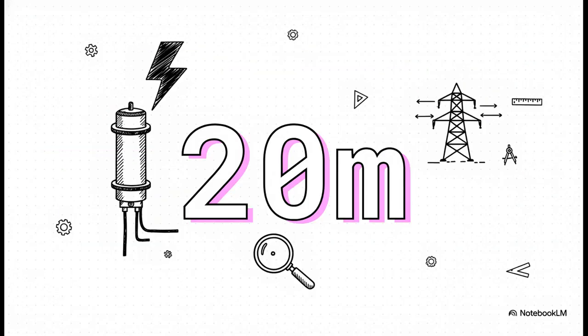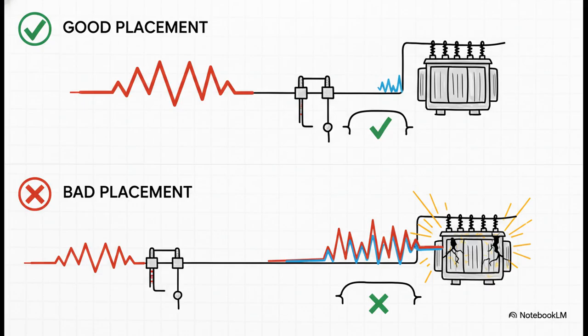Now, besides that rating, when it comes to actually installing one of these, there's a specific number that engineers are almost obsessed with. And it's probably a lot smaller than you think. 20 meters, that's it. For a typical distribution system, that is the absolute maximum effective distance you can put between an arrestor and the transformer it's supposed to be protecting. Any further away and the voltage can actually build back up in the wire between the two. So placement is everything. To be a good guardian, you have to be standing right next to the thing you're guarding.